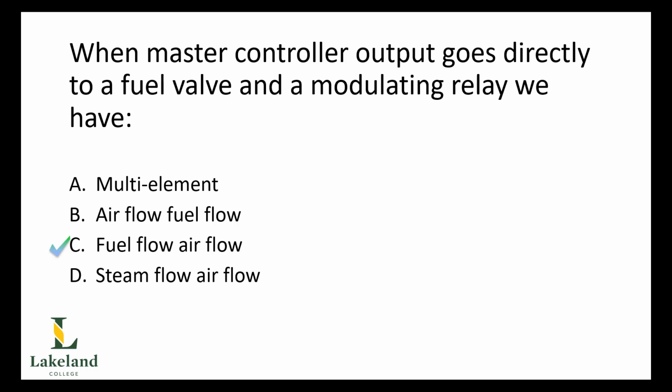When a master controller, that's going to be the pressure recording controller responding to drum pressure and the drum pressure transmitter, when its output goes directly to the fuel valve, which you can see on the diagram is located directly below the hand auto station, below the master pressure controller, that is then describing a fuel flow airflow controller.